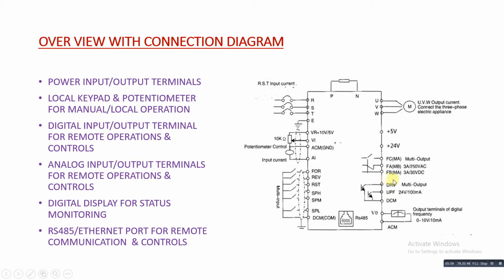Analog input output terminals are also available for remote operation, and a digital display for status monitoring. On any VFD you can see a digital display where you can see the frequency, current or voltage, whatever configuration you made, and monitor those units. Some VFDs also come with an RS485 port or Ethernet port. These are the major connections, terminals and facilities available in VFDs.